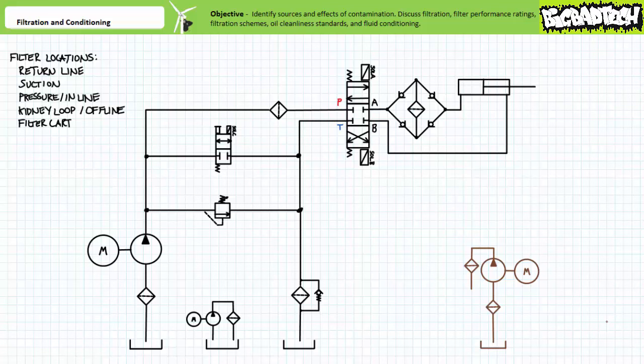A pressure or inline filter, in contrast, is a filter upstream of any valve or component in the system exposed to pressure. Pressure filters must be robust enough to handle these increased working conditions, and are often used to protect special purpose components necessitating special filtration requirements. An example might be some stuck-up hoity-toity valve that has no fondness for the dirty oil enjoyed by the rest of the common rabble. Note, ordinarily filters are meant to be unidirectional, since running a filter in reverse would blow out any previously entrapped contaminants and run counter to its intended purpose of cleaning the oil.